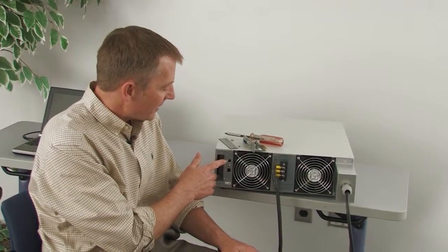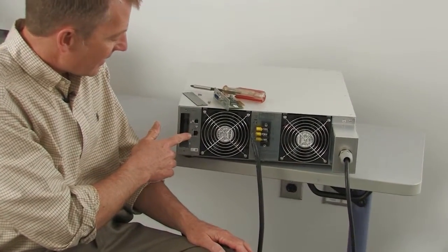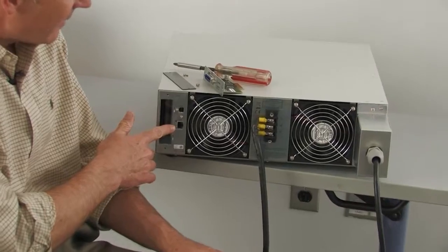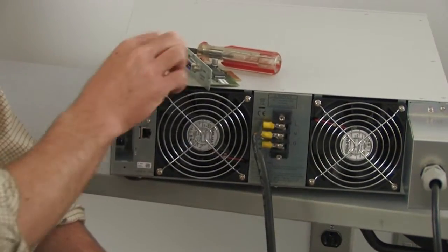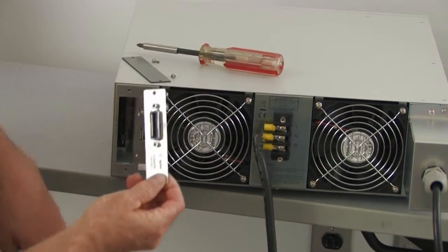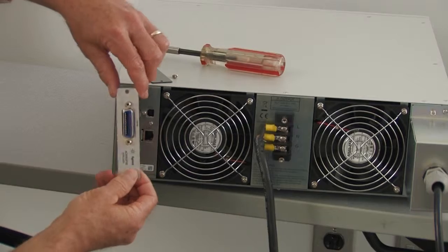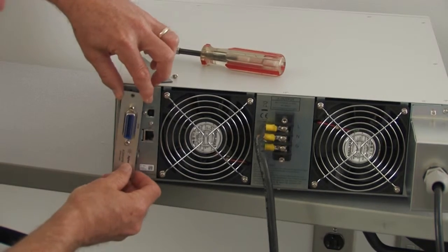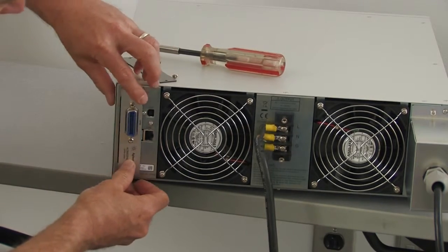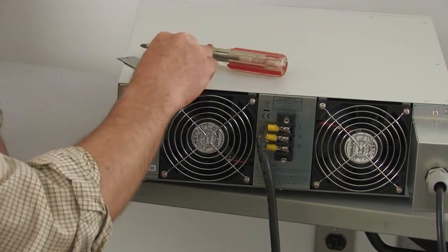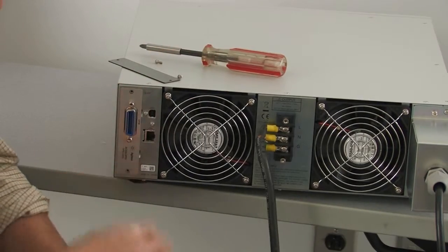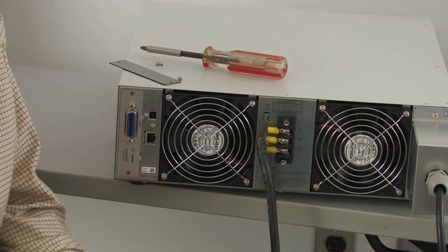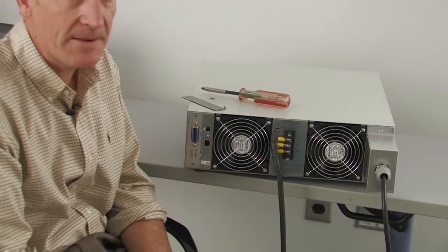It comes standard with a USB interface and also a LAN interface, and I've removed the filler panel and I'm going to install the optional GPIB interface. It just pops in, and then two Phillips screws are inserted and we're all done installing our optional GPIB interface.